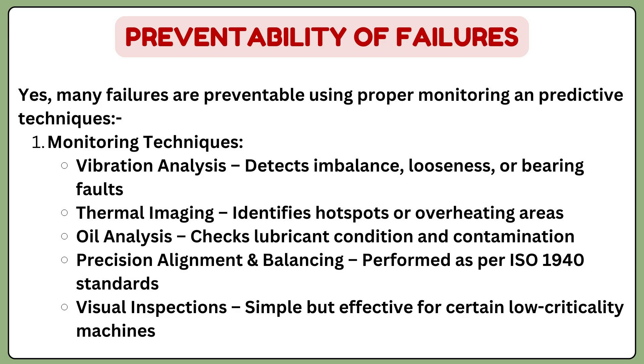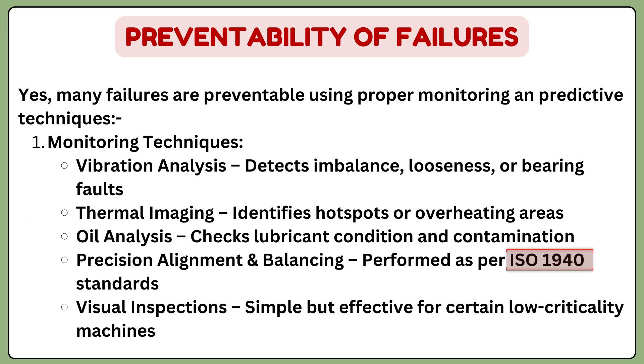The sixth question is whether these failures are preventable. The answer is yes or no. If yes, we identify what monitoring techniques can detect or identify them. For a process fan, you can use vibration analysis, thermal imaging, oil analysis, precision alignment, or precision balancing as per ISO 1940. All these preventable actions are mapped based on the criticality level or type of failure effect.